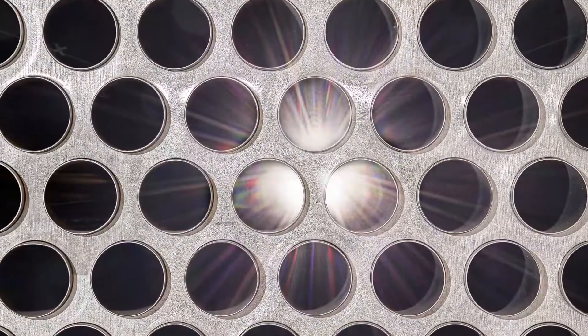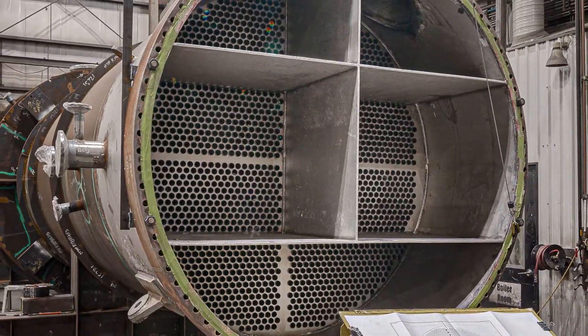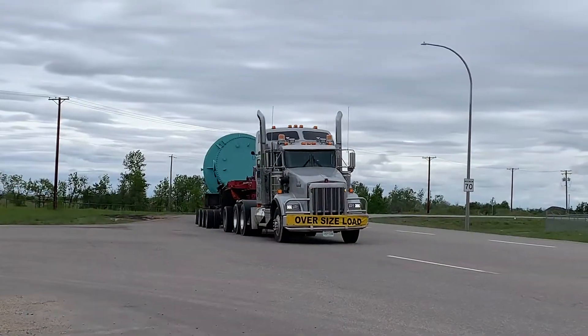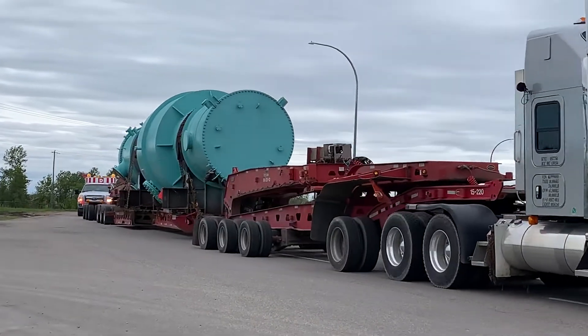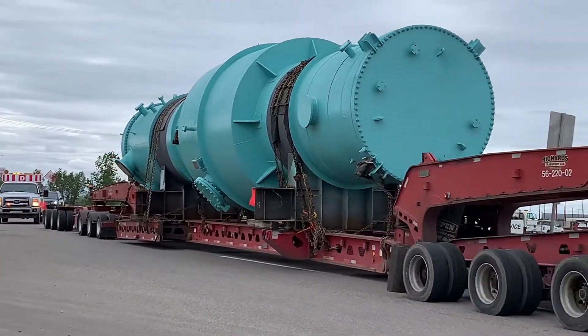If we didn't do it correctly, we'd have a very expensive sprinkler on our hands. Titanium work-hardens so quickly that we only had one chance to get it right. The scary part when we built the first one is we couldn't test the connections until they were all complete. When we filled the first condenser with water and pressure tested, we only had one leak due to a faulty tube. That was pretty phenomenal.